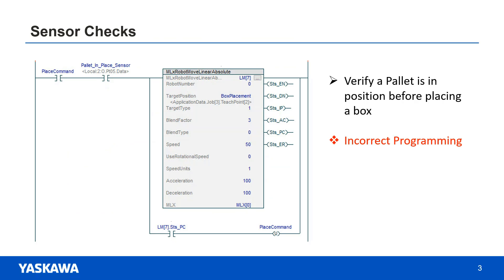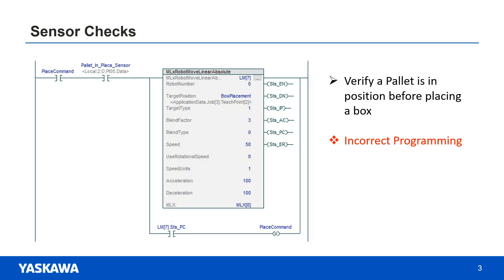A common mistake which can cause problems is to place a sensor input right before an MLX command. For example, you might want to make sure a pallet has moved into the correct location before a box is placed onto it. If the sensor has a weak signal and it flickers off and on for a short instant, the motion AOI will be commanded twice.